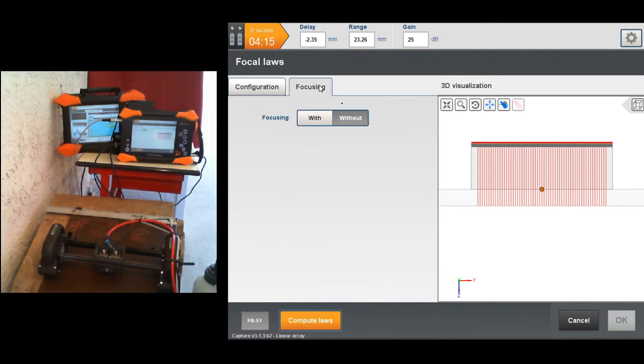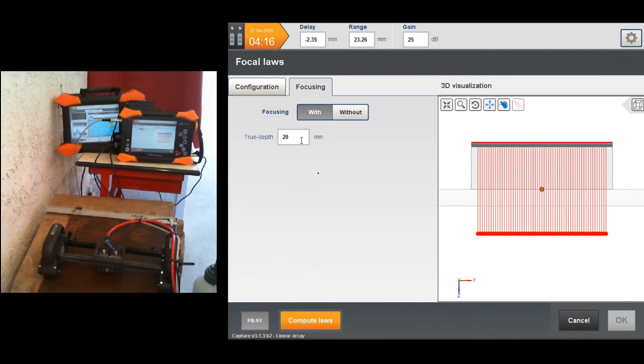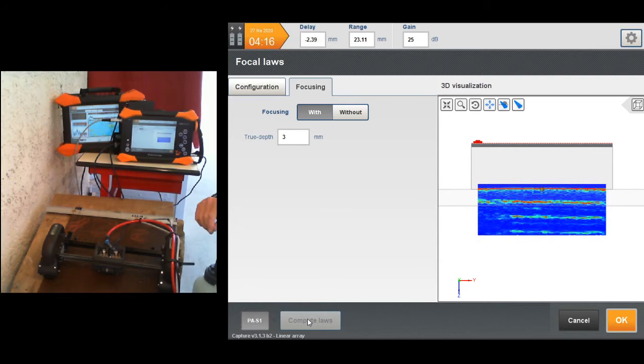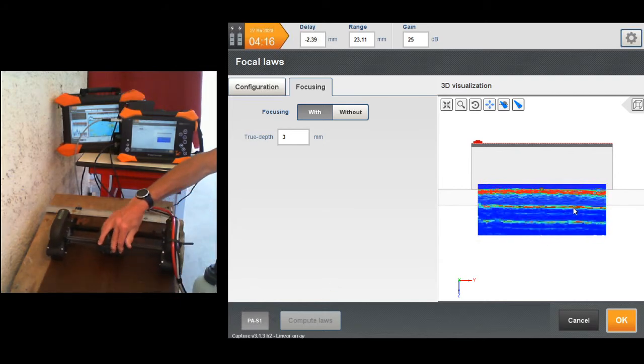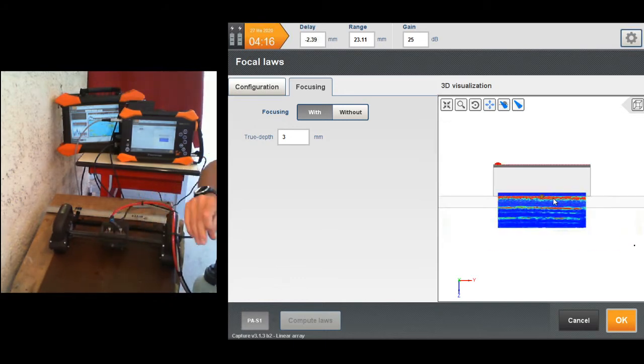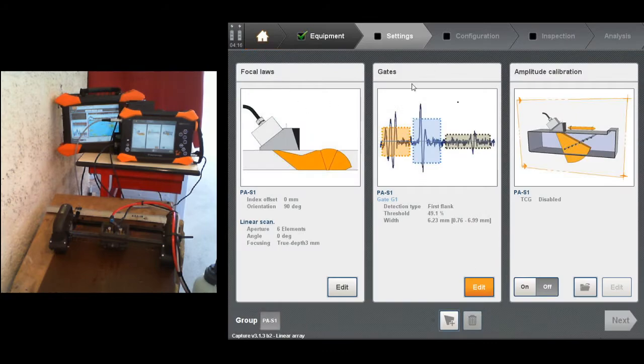Then focusing. In fact, with such a probe 6 by 7, I don't really know where my focusing point is. Natural focusing, which is the near field distance of this probe, is maybe further than the area of interest, and I don't want to use this beam in the near field distance or near field zone. So what I can tell the software, maybe if I give 3 millimeter as a focusing point, I know that the plate is 7, so from around 3 millimeter, I am perfectly safe, and my UT beam will be very good. So then I can compute, put a bit of water, still perfect, and then I can see I have some live signals. Okay, great, good. So I can accept this step, and with these focal laws. Now the next step is gates.